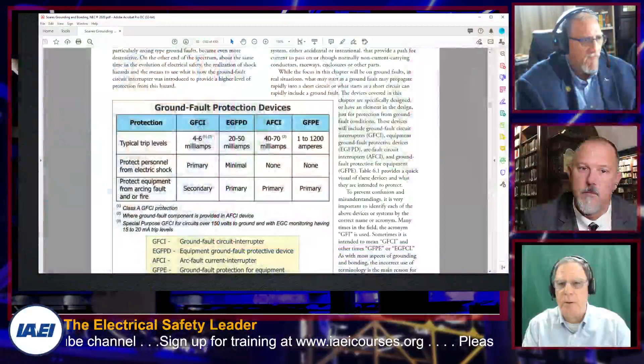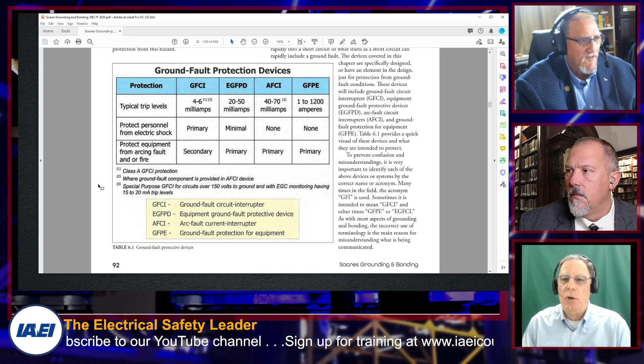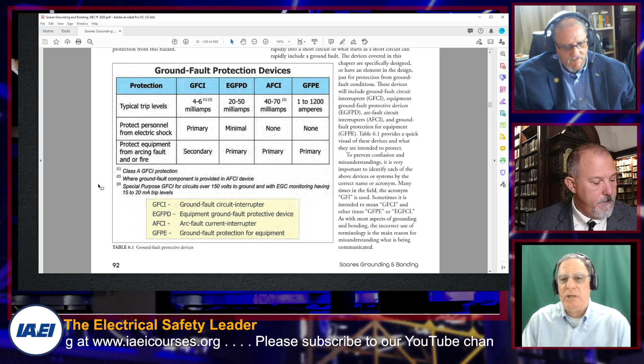And the key is that when you get into special purpose conditions, and why you have that robust equipment grounding conductor, what you're trying to do is keep the potential that the person is subjected to under 150 volts to minimize that shock hazard, that shock injury level they're going to have until the device can work. If you try applications of 480 volts or whatever with a typical Class A GFCI, you're going to have so much leakage just through the normal insulation, no problem, but that leakage is going to constantly be tripping that at the 4 and 5 milliamp trip levels. So that's why the special purpose has higher trip levels, but now you're mitigating that hazard more by having a more robust equipment ground conductor.